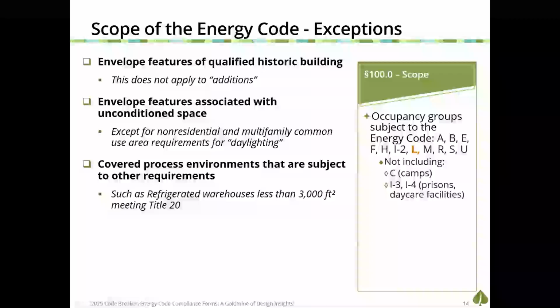Covered process environments are subject to other requirements. If I have a refrigerated warehouse less than 3,000 square feet, it's not subject to the energy code—it's subject to the appliance standards here in California, Title 20. But a refrigerated warehouse greater than 3,000 square feet is subject to the energy code, and everything about that environment and the equipment serving it would have to meet it. So we need to be aware of thresholds that fall under other code bodies versus the energy code.